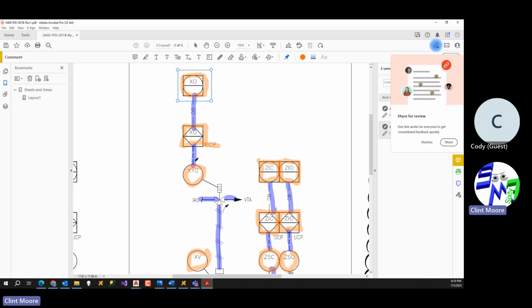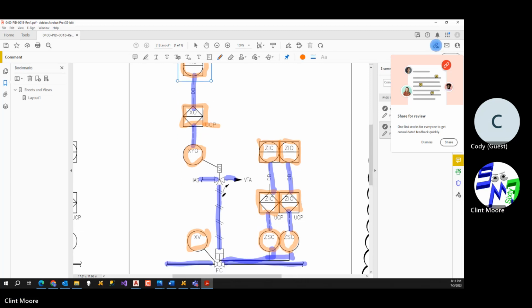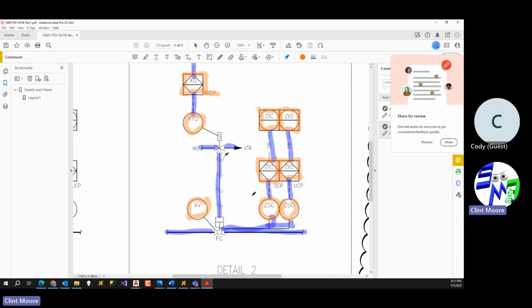This is the solenoid. Here is an electrical signal that comes to this solenoid and tells it to open or shut. Okay. When it closes, it lets the air come through here. When it releases, the instrument air will come in here and flow where it needs to be. So this is a three-way valve, essentially, and it's either letting hydraulic flow this way, or it's going to go straight across. So it depends on how this actually comes up. There's more in-depth discussion to go into that, but I'm just trying to get past it quickly.